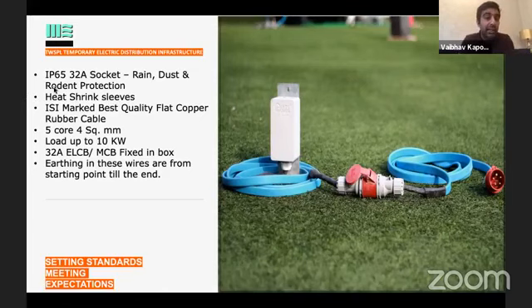Again, I'm using a socket. Heat shrink sleeves. You see the black sleeve is heat shrink. They are best quality. These are all rubber cables. Now, why am I using rubber cables? People are using PVC, aluminum, armored cables. Over a period of time, when exposed to weather, PVC tends to crack. Rubber doesn't. Rubber is flexible.